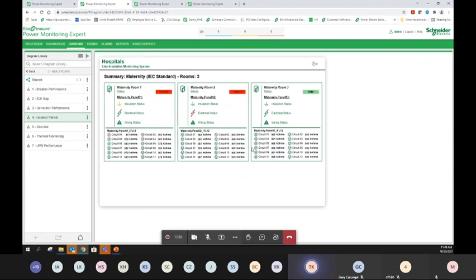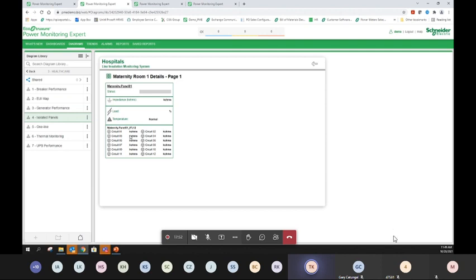And this information is actually coming from the insulation monitoring device, our insulation locator that Schneider has. So this IFL is one of the Schneider products that can measure up to 12 channels of impedance. You can see that we have our insulation fault. There is going to be an insulation failure in this time period. It has reached 40 kilo rather than the 200 kilo it should be. So we go into the setting: the impedance is 30 kilo, but you are always going to be close to 30 kilo. This is why the software will flag the alarms that you have impedance.